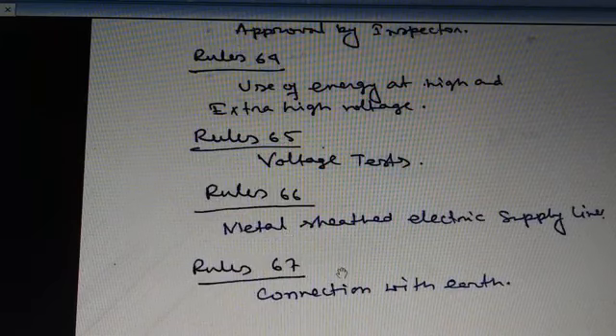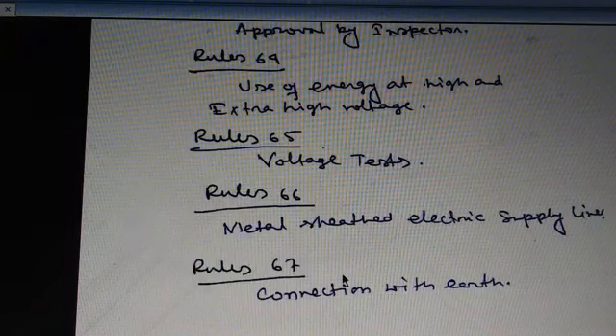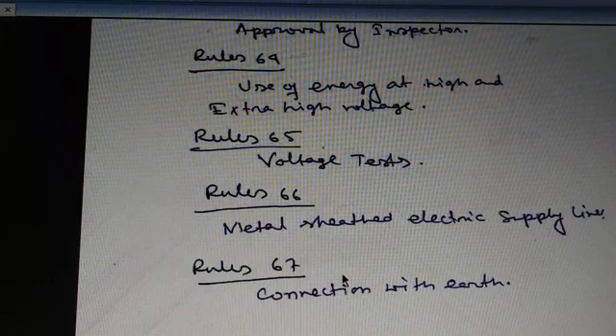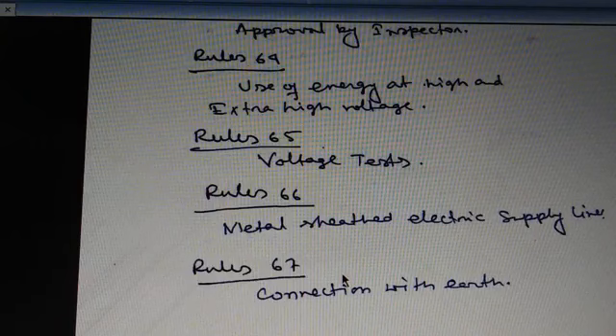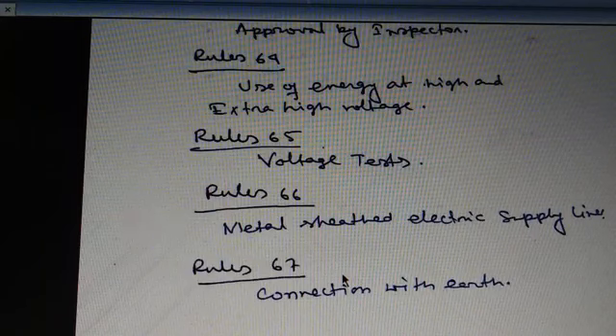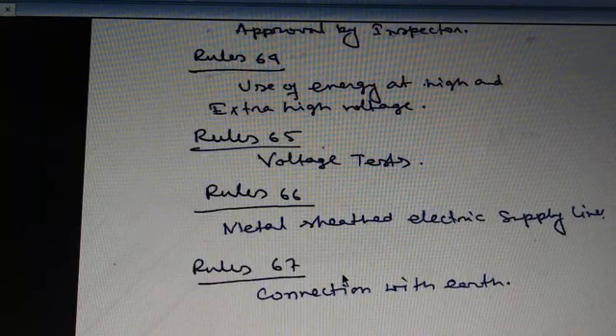Now rule number 67, connection with earth. The following provisions shall be applied to the connection with earth of three-phase system for use of high and extra high voltage. Number 1, the neutral point shall be earthed by not less than two separate and different connections with the earth.